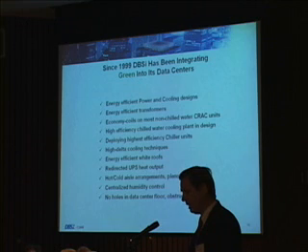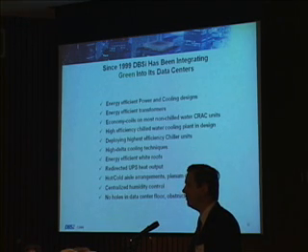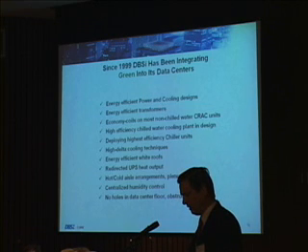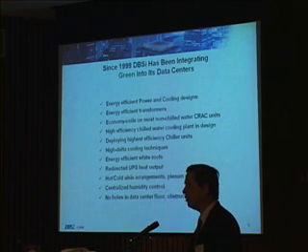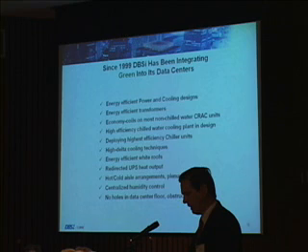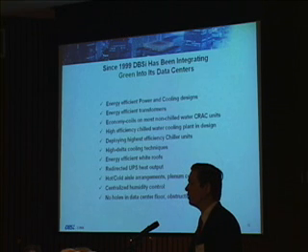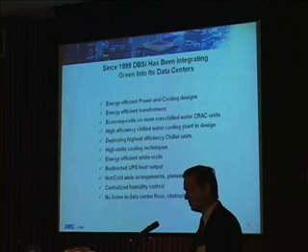Redirect UPS output heat: we send that out into our shipping and receiving areas and to our generator buildings, so we don't have to run as much heat out there in the wintertime. Central humidity control, and we've taken all the holes out of the data center floor, so there's no air leakage behind the cabinets.